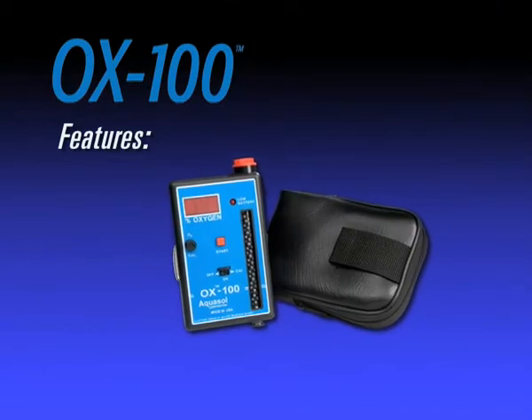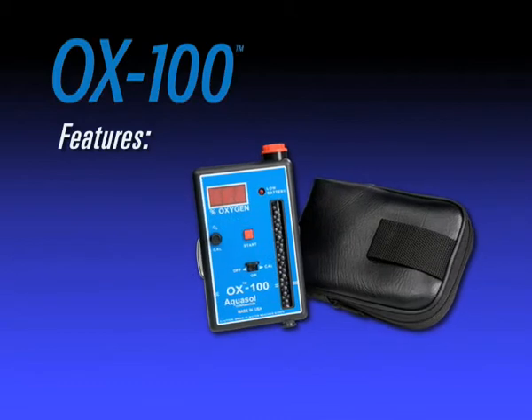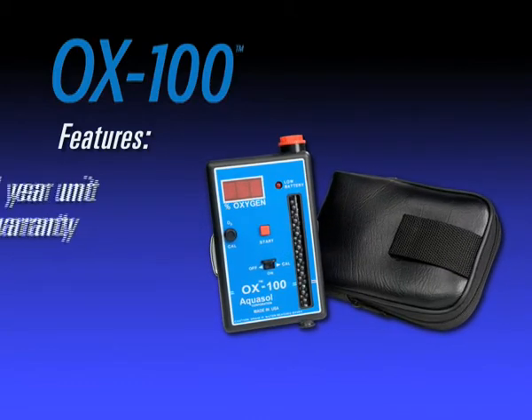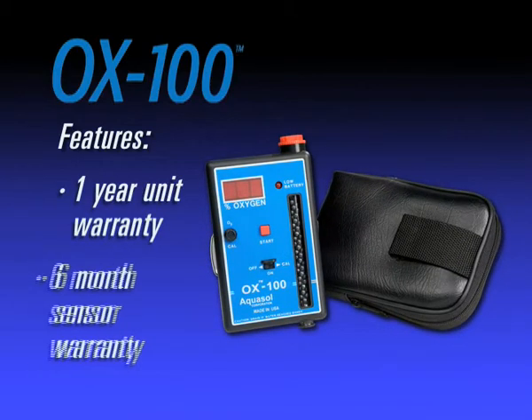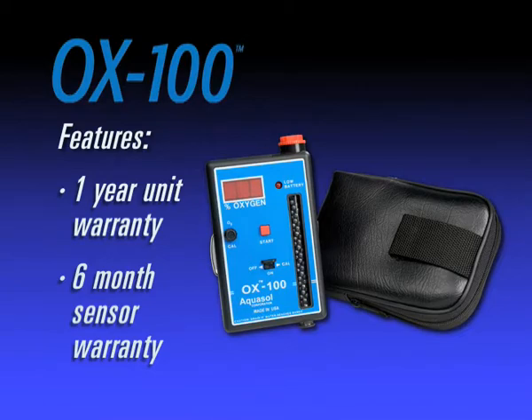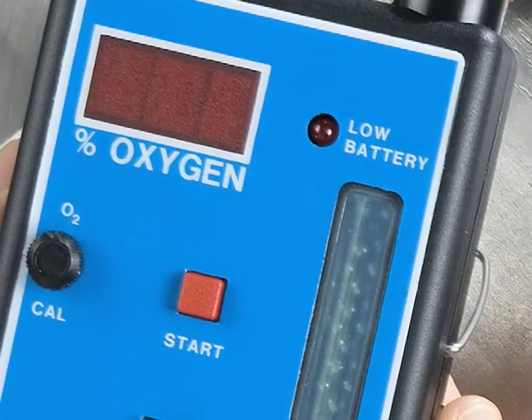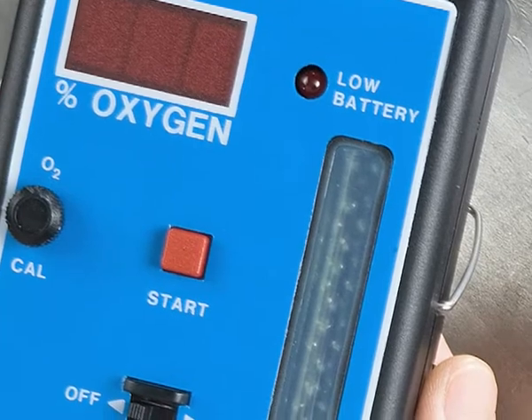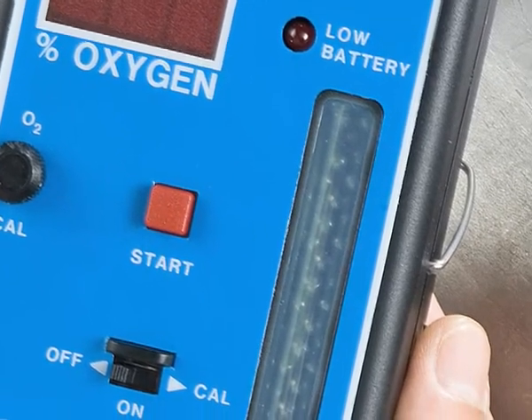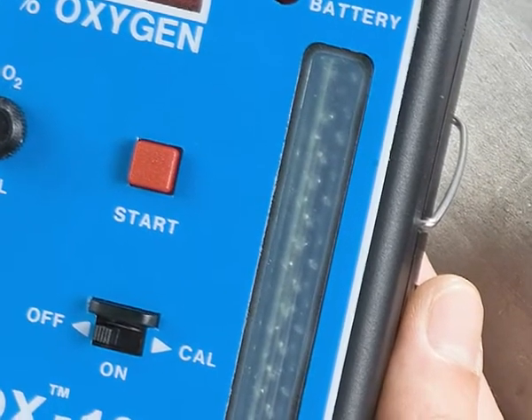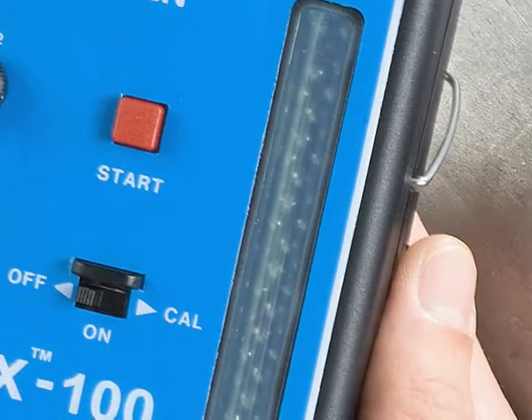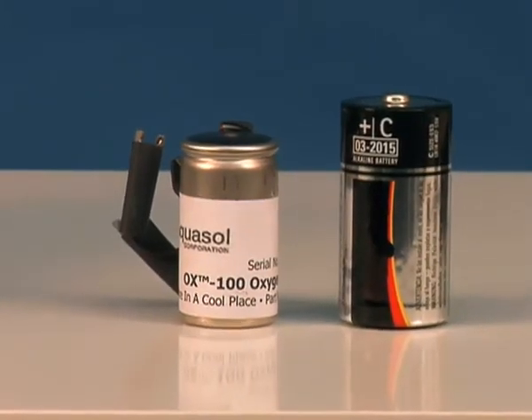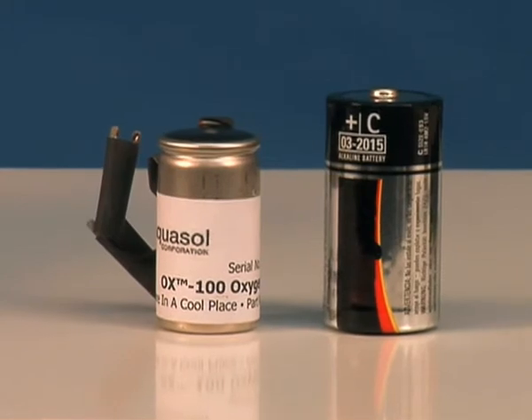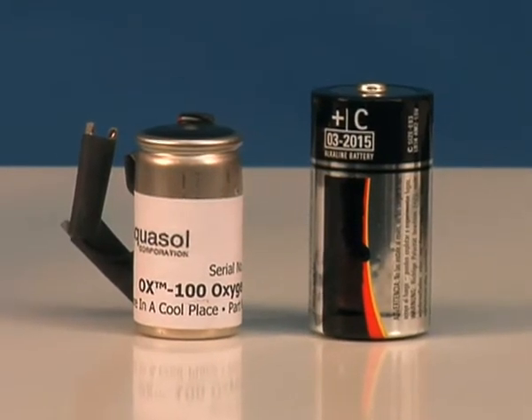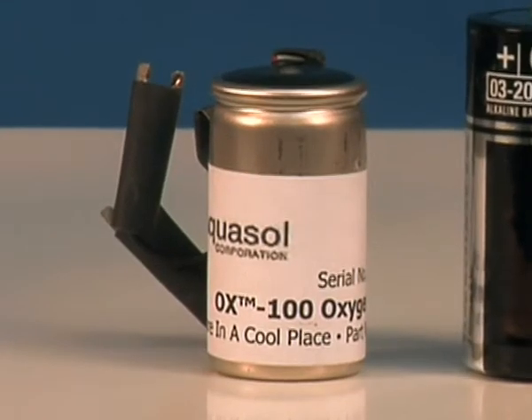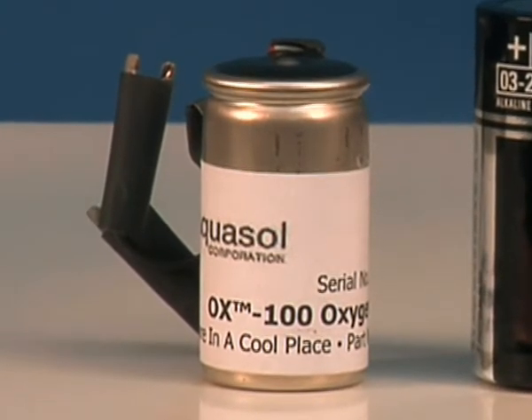When it comes to performance, the OX-100 offers superior advantages, including a 1-year warranty on the unit and a 6-month warranty on the sensor. The line filter and internal moisture trap prevents any contaminants from reaching the oxygen sensor. The oxygen sensor itself easily calibrates with ambient air. The oxygen sensor is a small fuel cell that measures oxygen volume directly. The size of a C-cell flashlight battery, the Aquasol oxygen sensor is disposable.